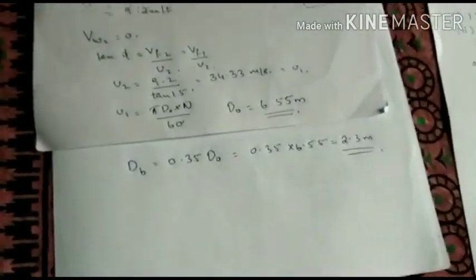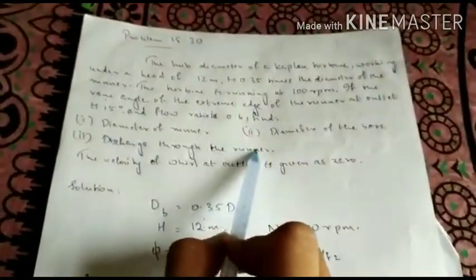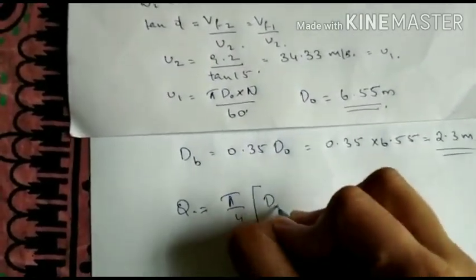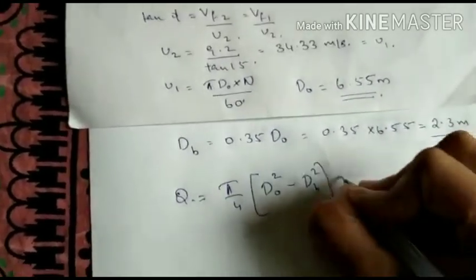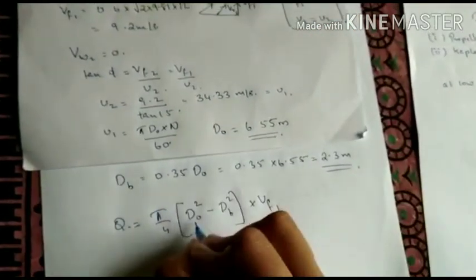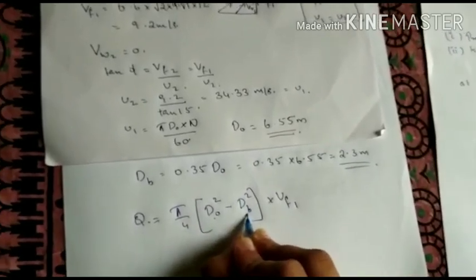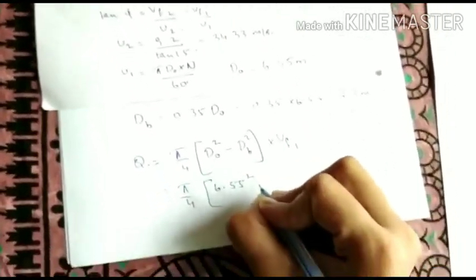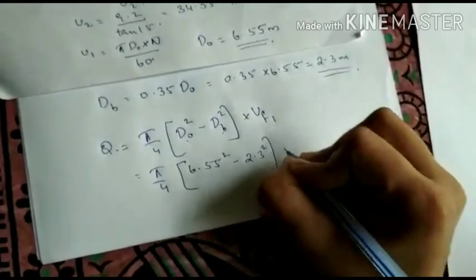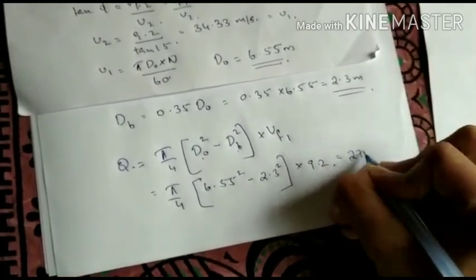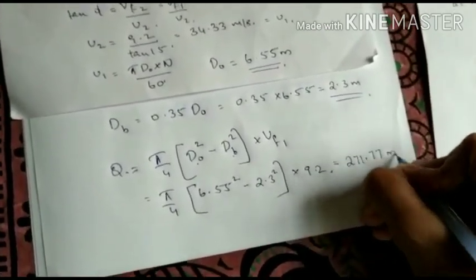Now discharge through the turbine is the third part of the question. Discharge through the runner. So Q is equal to pi by 4 into D0 square minus Db square into VF1. So all these are given. This is the diameter of the hub, diameter of the runner and this is the inlet velocity. So pi by 4 into 6.55 square minus 2.3 square into 9.2. And you will get it as 271.77 meter cube per second.